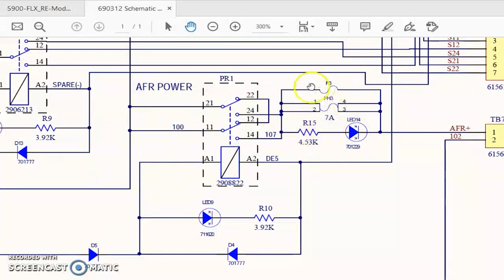Now, all of this up here has to do with what the switch contacts of the relay are doing. So this is irrelevant. Don't even think about this for right now. But remember, voltage is just like pressure. So if I measure voltage between a ground point in the panel and any of these points along here in the schematic, I'm going to have 24 volts.